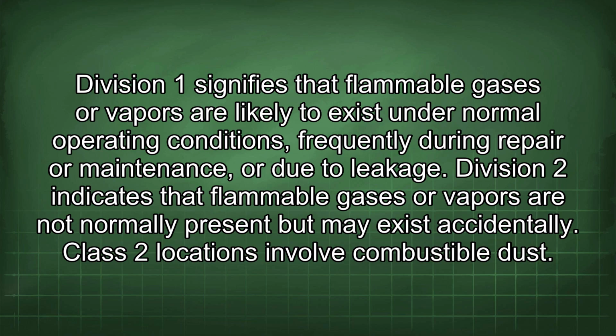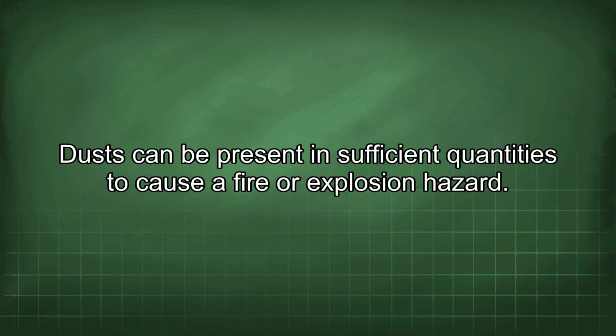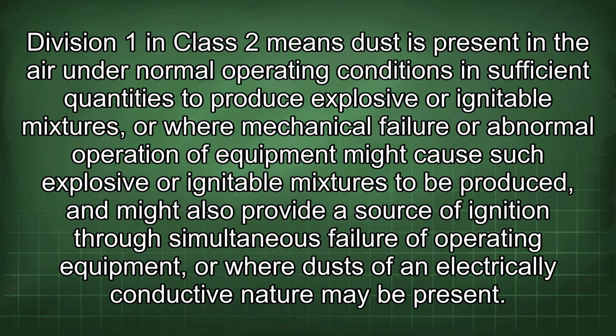Class 2 locations involve combustible dust. Dust can be present in sufficient quantities to cause a fire or explosion hazard. Division 1 in Class 2 means dust is present in the air under normal operating conditions in sufficient quantities to produce explosive or ignitable mixtures, or where mechanical failure or abnormal operation of equipment might cause such explosive or ignitable mixtures to be produced, and might also provide a source of ignition through simultaneous failure of operating equipment, or where dust of an electrically conductive nature may be present.